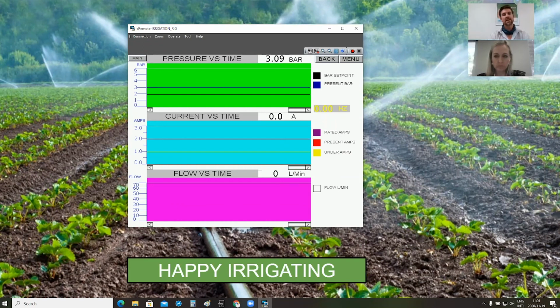It's very important that you get the voltages right when you are designing your solar array, so that the maximum power point voltage of your panels is quite equivalent to where Eskom would be. If you want to chat more about it, we can do offline. I did go into more detail on that on the hybrid setup. But yes, it is possible to add solar panels to the irrigation system, and remember that you're controlling on pressure, not on solar radiation.